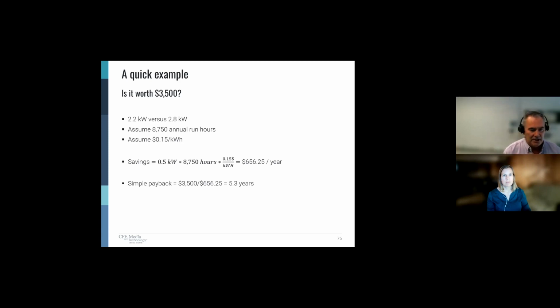Depending on what this motor is connected to, an air handler for example, 5 years is nothing. We see air handlers in the field that are 15, 20 plus years old. So this motor would pay for itself 4 times over. That seems like a pretty good deal to me.